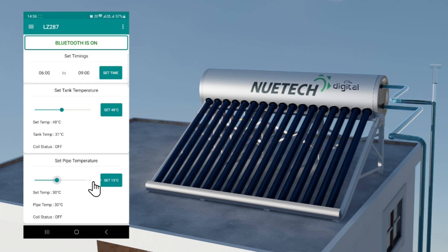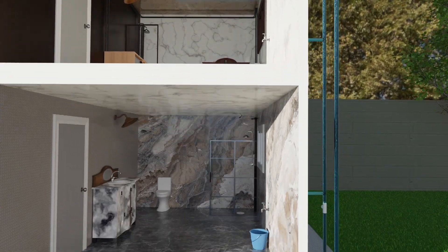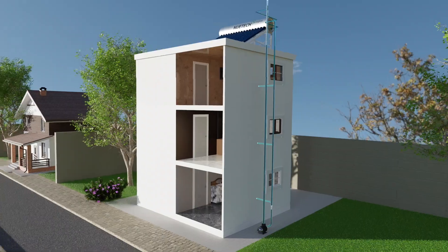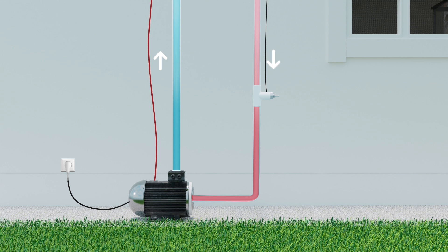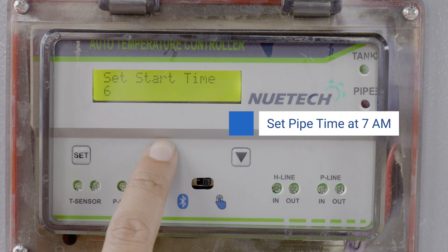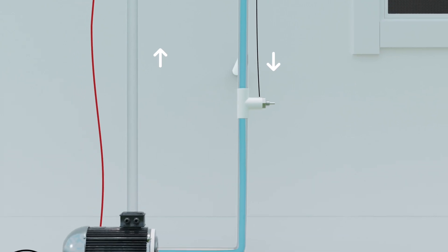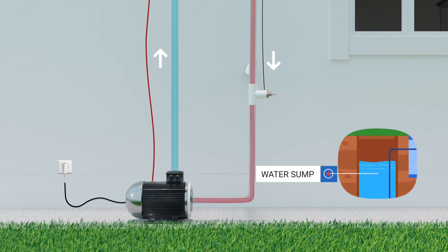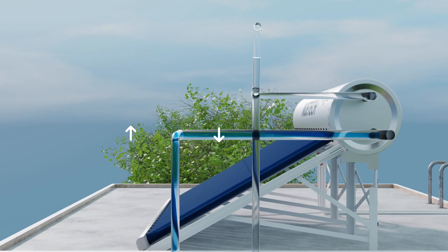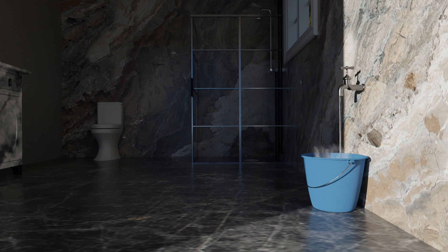You can see the real-time temperature in the application. For return line plumbing and electrical connection: the solar tank's hot water line will be connected to all the bathrooms. Place the sensor near the end bathroom, then continue the pipe and connect it to the motor inlet. Connect the motor outlet to the solar tank cold water inlet or sump. In accordance with the time and temperature settings, the sensor operates and the cold water in the outlet moves to the tank or sump. The water heated in solar flows into the outlet pipe, so once we turn on the tap, we immediately get water at the set temperature.